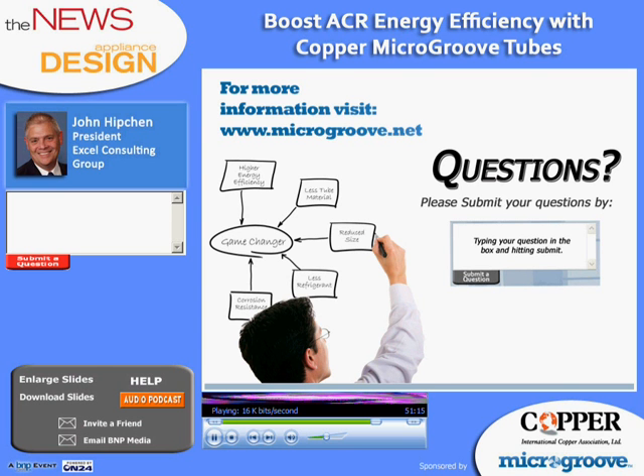Okay. Is there a pressure threshold concern with the smaller diameter tube walls? Well, I'm sure, eventually, if you continue to increase the pressure in a round tube or any tube, it will eventually burst. So there is a pressure threshold, but you can achieve much higher pressures with a smaller diameter tube than you can with a larger diameter tube when you're looking at the tube wall thickness. So as you saw in the case studies, I believe we had a tube wall thickness of about 0.28 millimeters in the 9.52 millimeter tubes and the 7 millimeter tubes. That tube wall thickness was reduced to 0.2 millimeters, which is a considerable drop in wall thickness and leads to a considerable drop in materials from a weight standpoint.